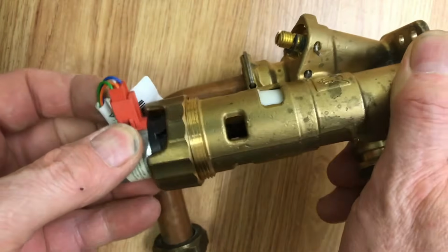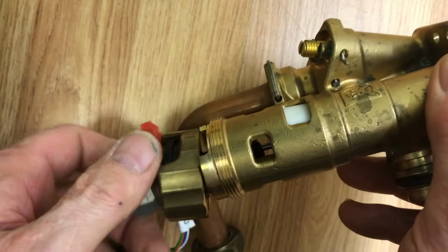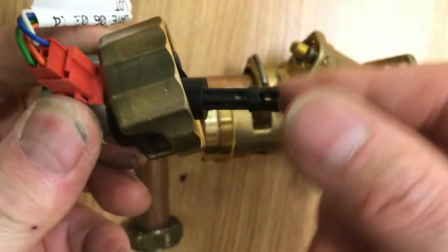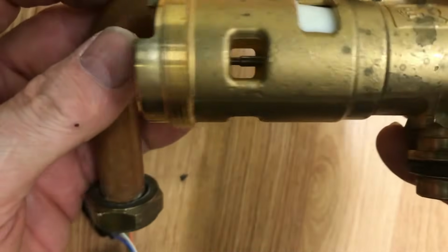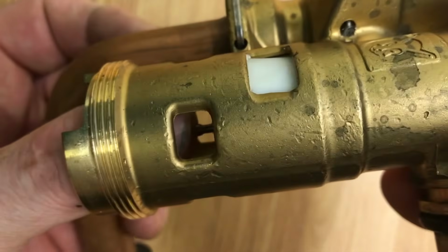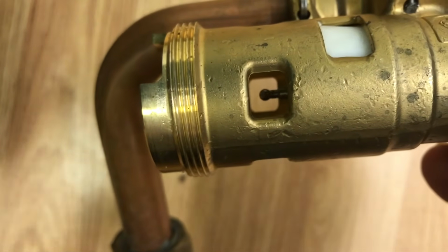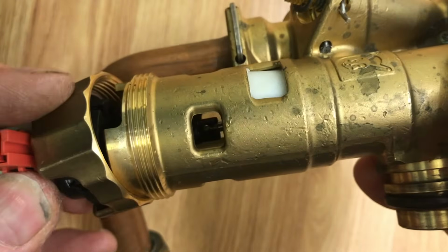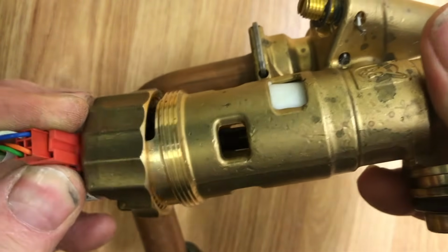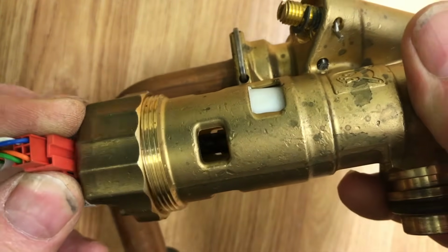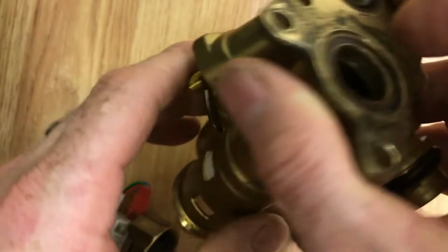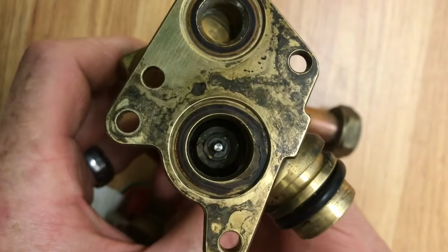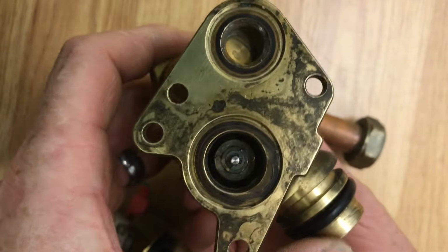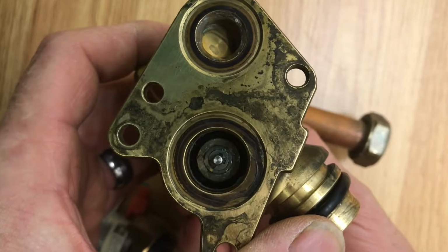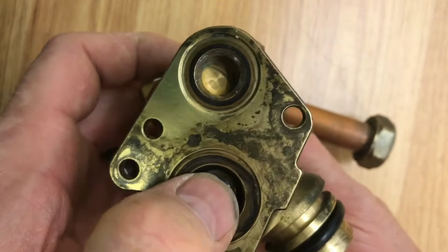So, okay, now inside the hole there, you should be able to see the motor and how we can get it off. So if we look at this here, this clamp, so you can see how it's shaped. Actually, if I push the shaft back, you should be able to see it. You can see the little ball on the end of there. So that little ball clips onto this. So it goes over the top and clips up. So the motor drives the shaft in and shuts off the diverter valve. So if I push the plunger up, that pushes and closes off the port to allow the water to go around the system.